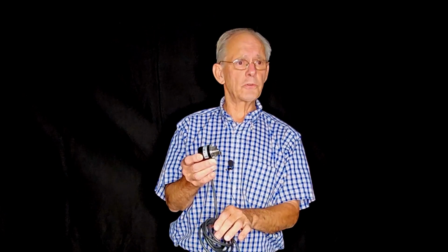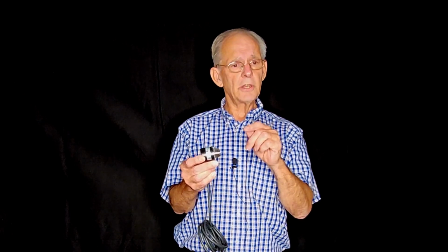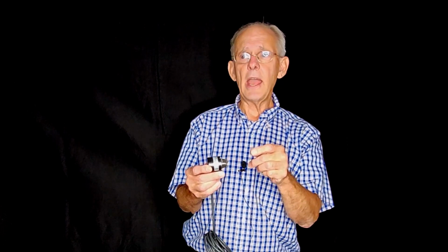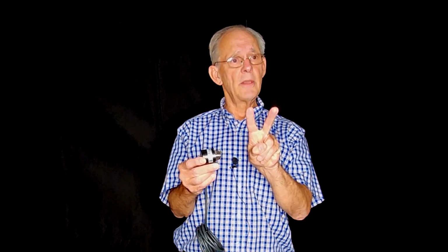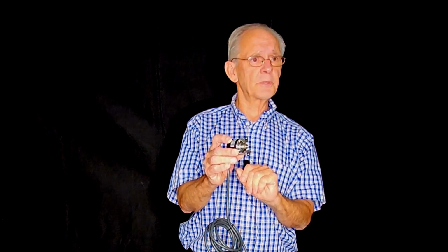That's called quadrature. By having the 2 phases out of sync, you can tell the direction of rotation and how fast it's going. It turns on 1 channel, then 2 channels, then only this channel, then only that one, giving 4 different signals - quadrature. By the sequence they go on in, you can tell what direction something is going.